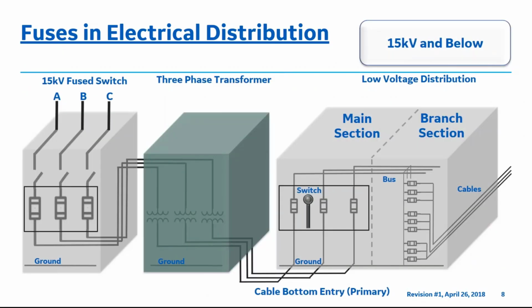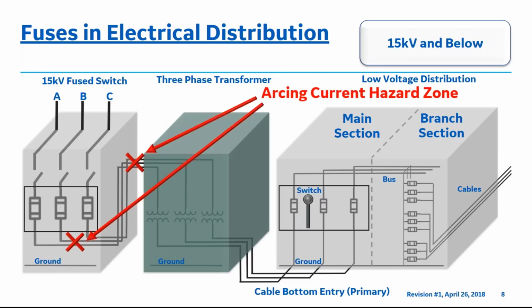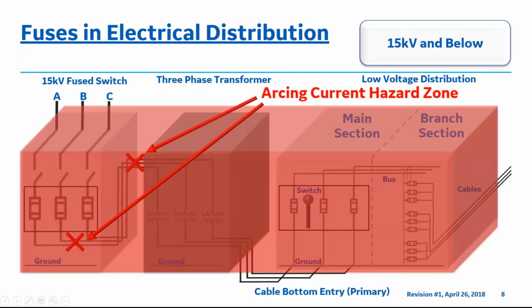This presentation will begin to address various areas where arcing faults occur in electrical power distribution systems for fuses. The first example of an arcing fault is between the 15 kV fuse switch and the transformer primary. If busway or cable connections, top exit, side exit, or bottom exit between the 15 kV fuse switch and the transformer primary are utilized, during these arcing fault events, the hazard zone consists of a 3-dimensional area around the fault shown here.